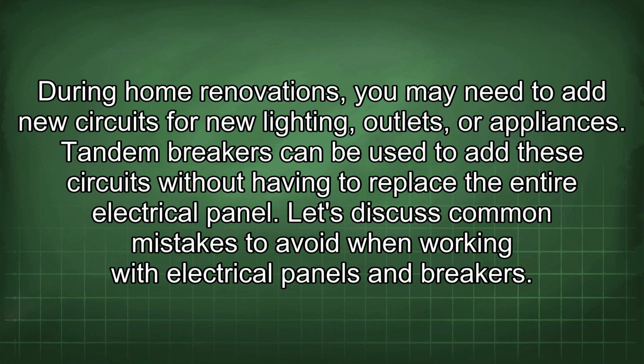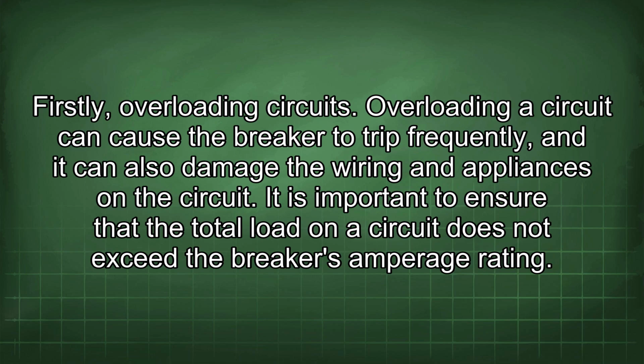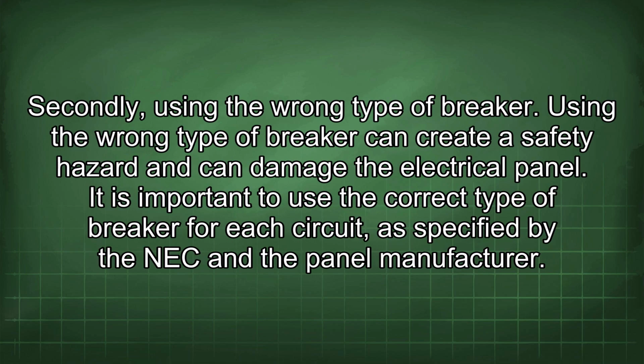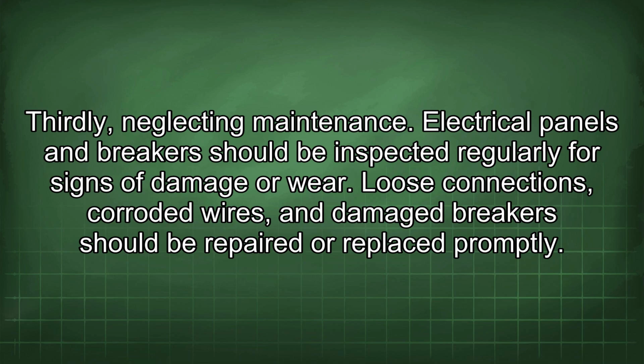Let's discuss common mistakes to avoid when working with electrical panels and breakers. Firstly, overloading circuits. Overloading a circuit can cause the breaker to trip frequently, and it can also damage the wiring and appliances on the circuit. It is important to ensure that the total load on a circuit does not exceed the breaker's amperage rating. Secondly, using the wrong type of breaker. Using the wrong type of breaker can create a safety hazard and can damage the electrical panel. It is important to use the correct type of breaker for each circuit as specified by the NEC and the panel manufacturer. Thirdly, neglecting maintenance. Electrical panels and breakers should be inspected regularly for signs of damage or wear. Loose connections, corroded wires, and damaged breakers should be repaired or replaced promptly.